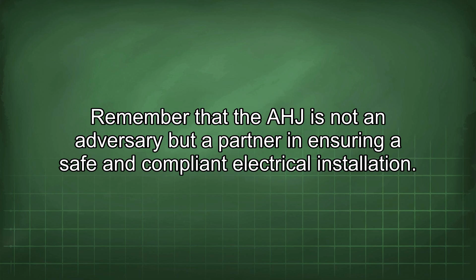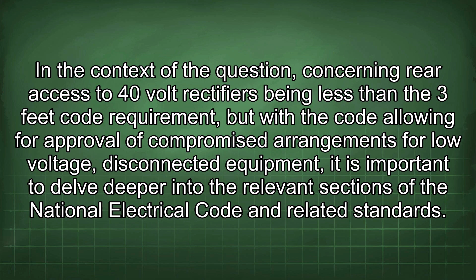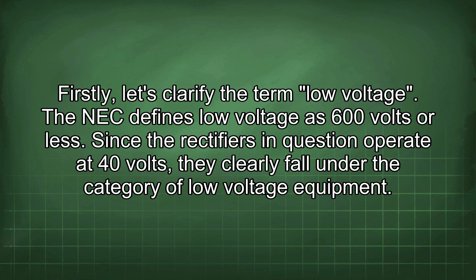In the context of the question concerning rear access to 40-volt rectifiers being less than the 3 feet code requirement, but with the code allowing for approval of compromised arrangements for low voltage, disconnected equipment, it is important to delve deeper into the relevant sections of the National Electrical Code and related standards. Firstly, let's clarify the term low voltage. The NEC defines low voltage as 600 volts or less. Since the rectifiers in question operate at 40 volts, they clearly fall under the category of low voltage equipment.